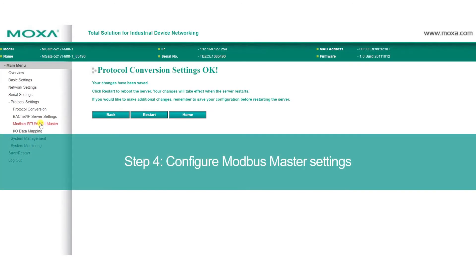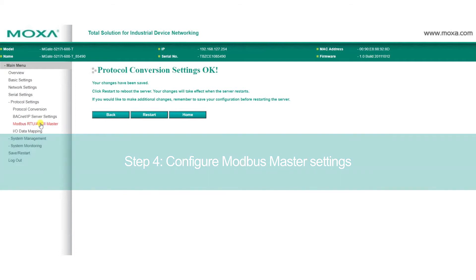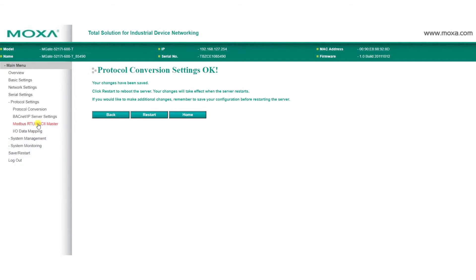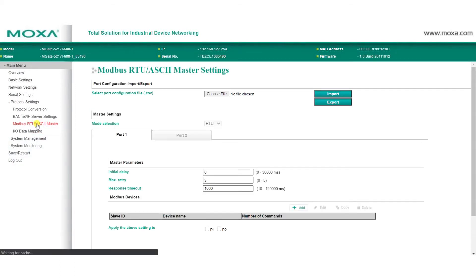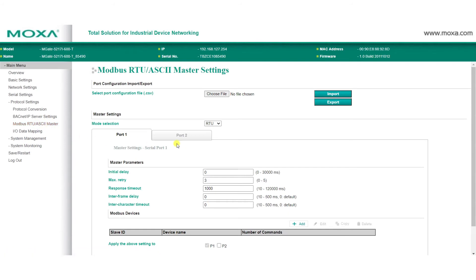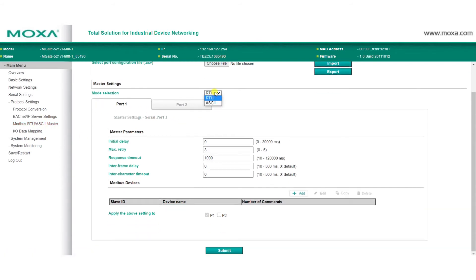Because we selected Modbus RTU ASCII for our protocol, the MGate will act as a Modbus master, and we can configure the related settings by clicking on Modbus RTU ASCII Master. Here, select which Modbus mode will be used. To monitor the power data from the power meter in our demo, we need to click Add to add our Modbus device.